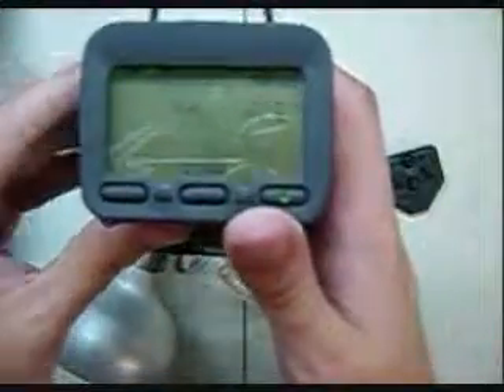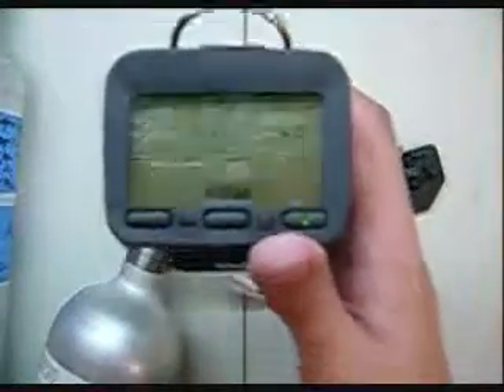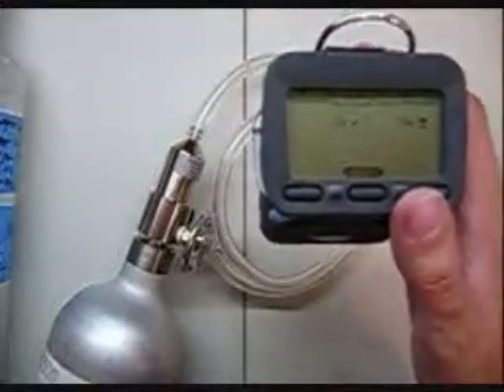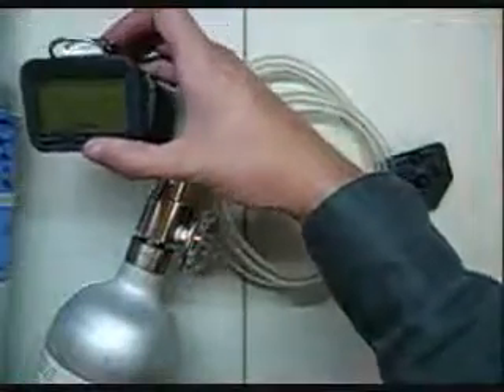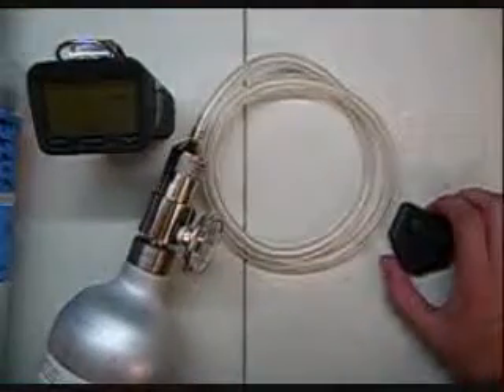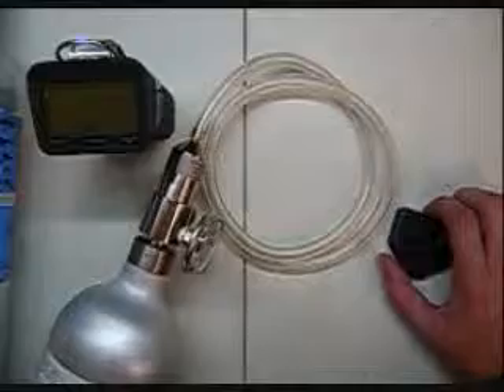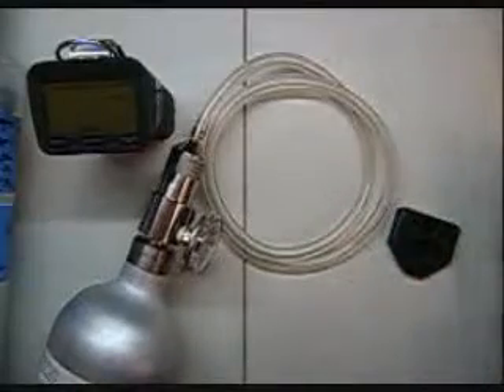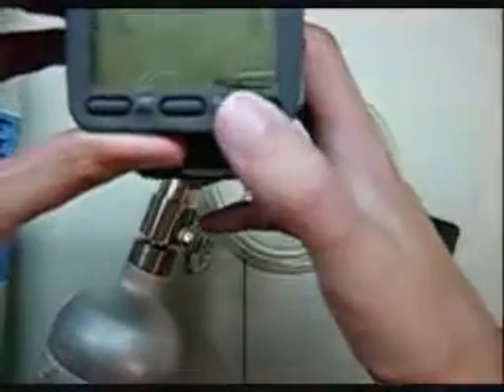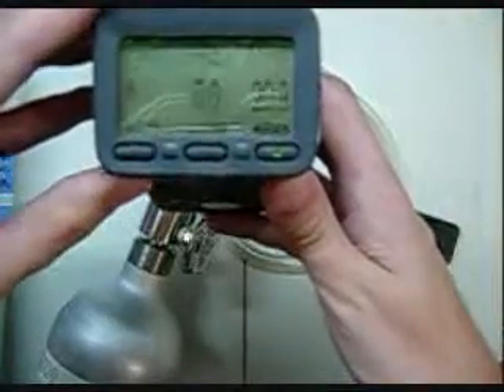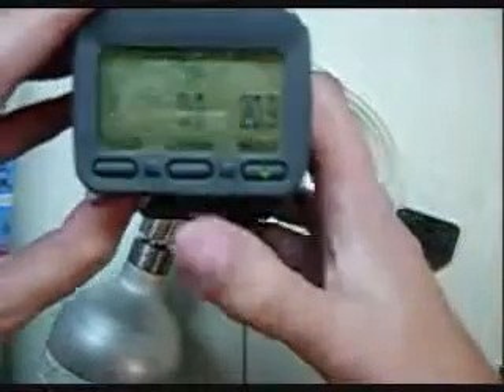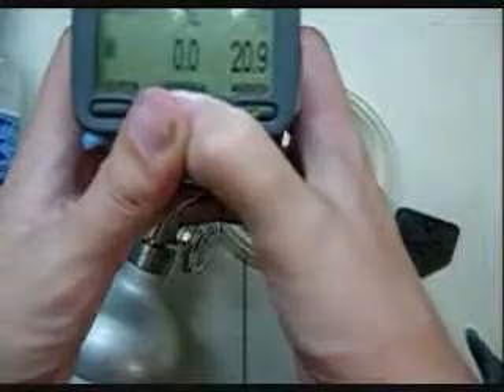You're going to notice on here I only have 2 sensors. Yours will have 4. But you'll see the O2 already has a check mark. The check mark means everything is good and that it's zeroed, or in this case with oxygen, calibrated correctly. You can see the CH4 sensor takes a little bit longer than the others. So just let that sit for a minute. Now it comes up and says they're all okay. It'll beep and head back to detection mode.